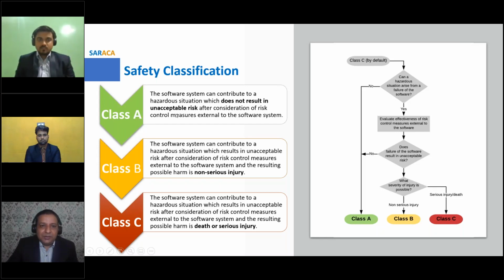But in general, class A software is one which does not result in unacceptable risk. If you're able to prove, using your software failure mode effect analysis, that your software does not result in unacceptable risk. And we have this debate many times with our customers. They say, oh, my software is very simple. It doesn't do anything. The device which is using it is not really next to the patient. And our question is that your classification of medical device is not based on your interpretation. It is based on your risk analysis.